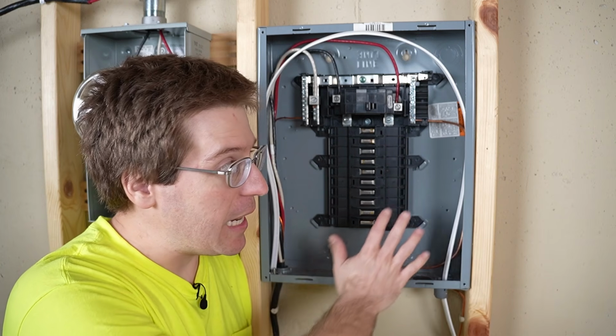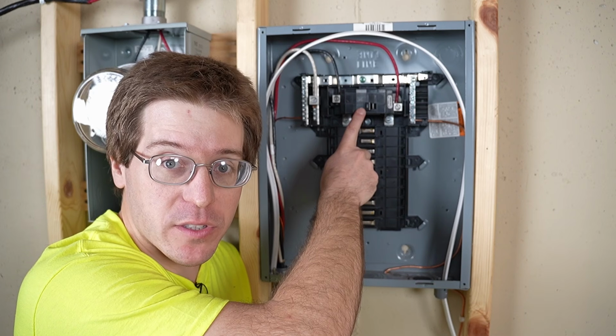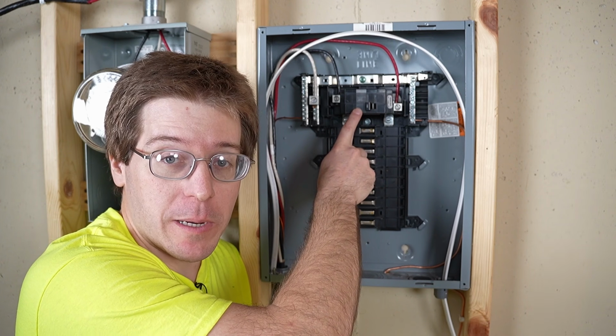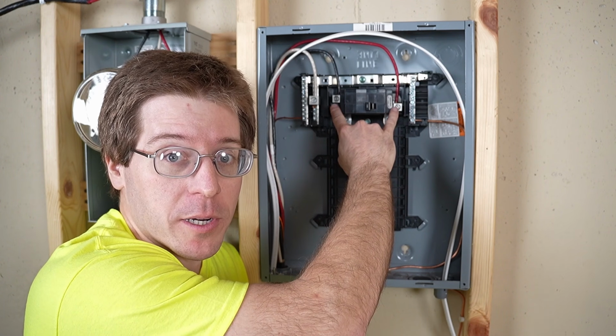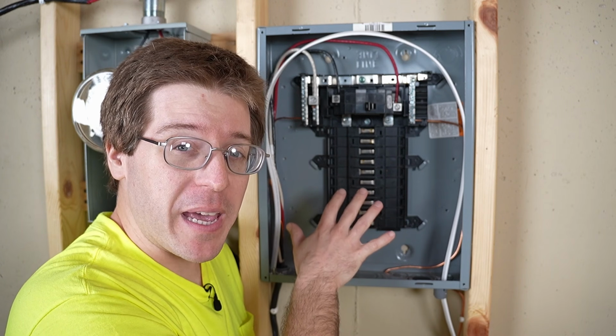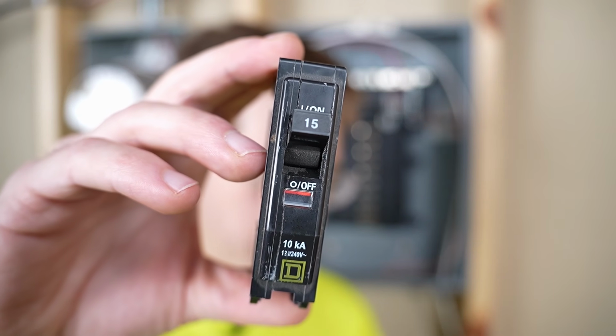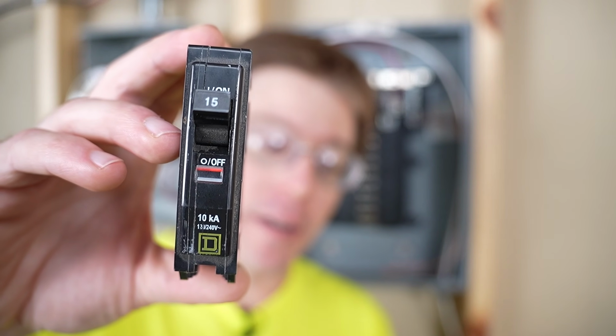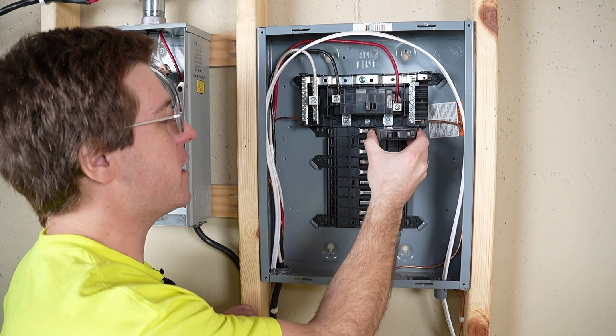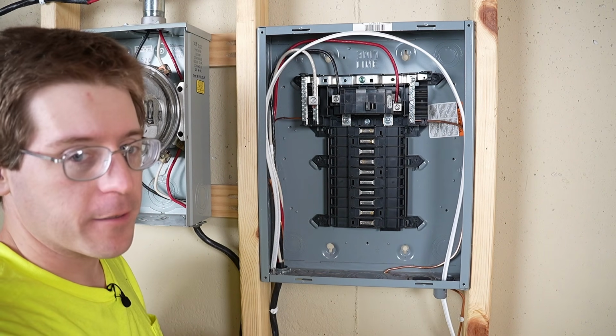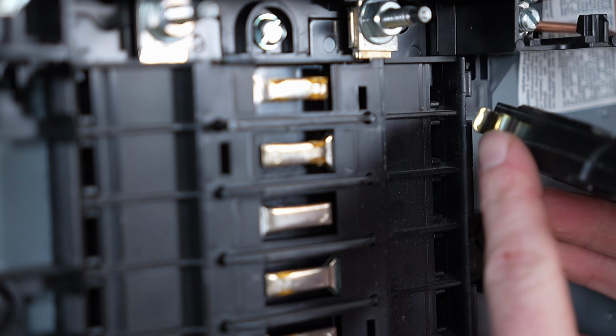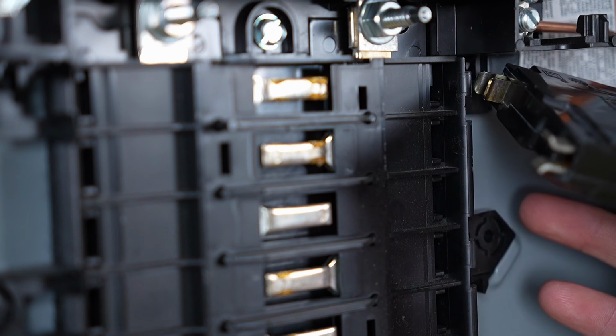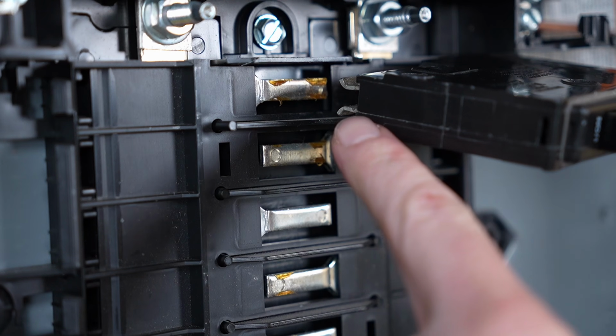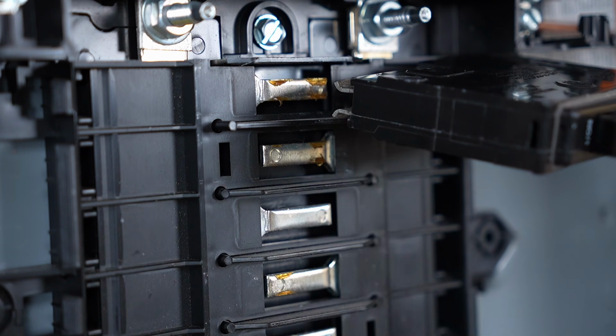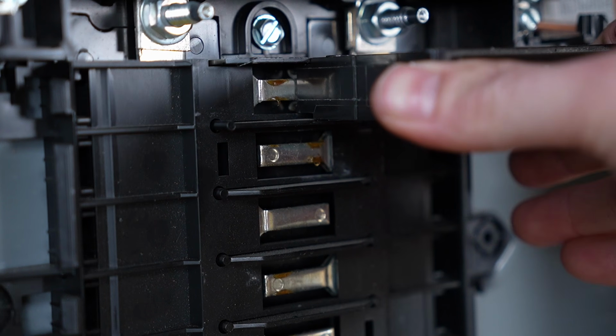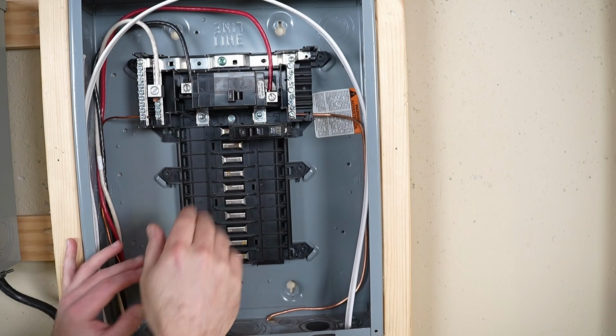As I mentioned before, anytime you work in an electrical panel, make sure your main circuit breaker is off. But when your main circuit breaker is off, there are still live terminals within your panel. So if you're working in an electrical panel, make sure you're qualified to do so. As I mentioned before, we're going to be installing a 15 amp circuit breaker. I am arbitrarily going to install this particular circuit breaker in this top position here. The way this particular panel works is there is a clip in the back here that clips on this plastic piece right here. And then on the main bus bar, there is actually a terminal that clips on it as well.